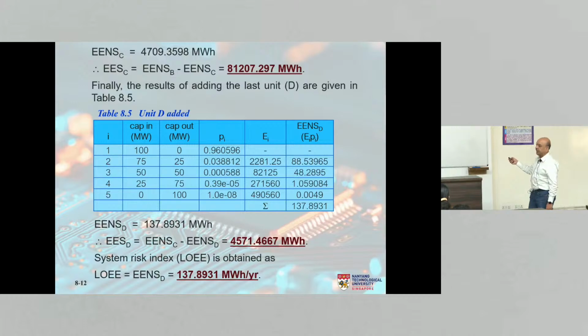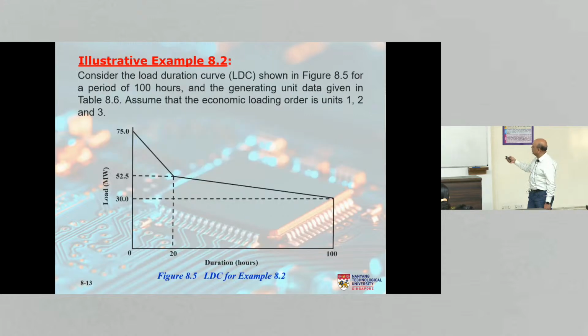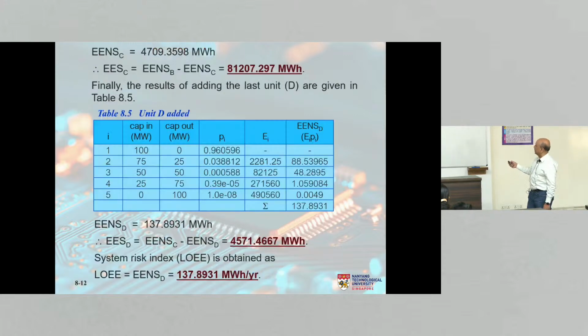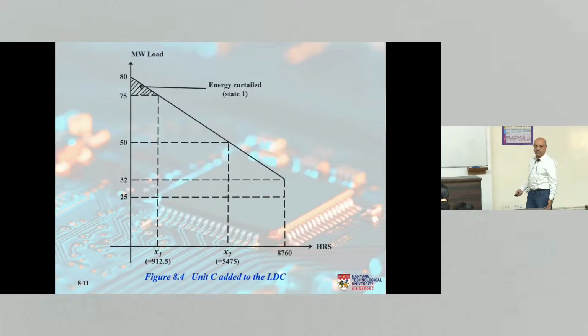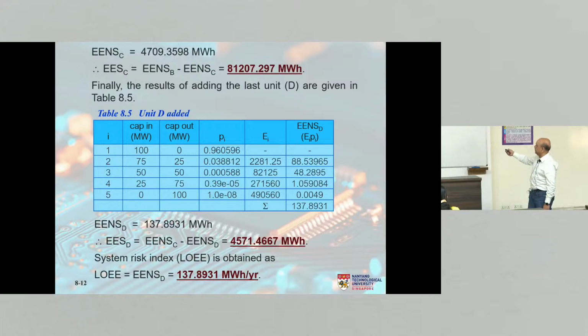Finally, you add the last generator, and this is your new capacity table, and you need one more value. But do you? What is that one more value? 100 megawatt is in, 0 megawatt is out. So if you look at that, you are not curtailing any load, right? You are not curtailing any load because your installed capacity is 100 and the peak load is only 80. So therefore, there is no energy curtailed due to that. So it's 0. So this is also 0. You can add up the rest and you get this amount.